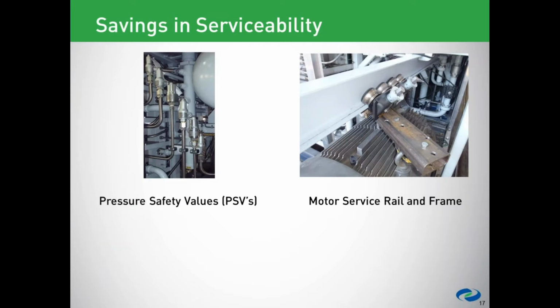All of the relief valves are easily accessible from a doorway on the back side of the package adjacent to the air outlet louvers. This really helps with ensuring that the relief valves are certified and recertified on a regular basis. They are easily accessible, can be disconnected by undoing some compression fittings, removed, tested, recertified, reinstalled very easily. No clambering inside the package between a jungle of tubing. They are all easily accessible directly inside of that access door.